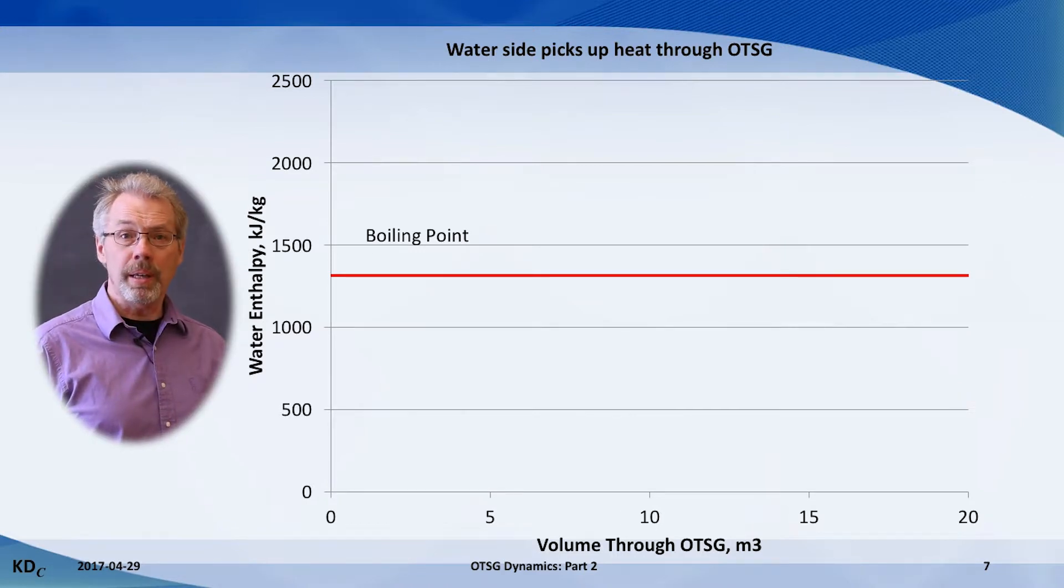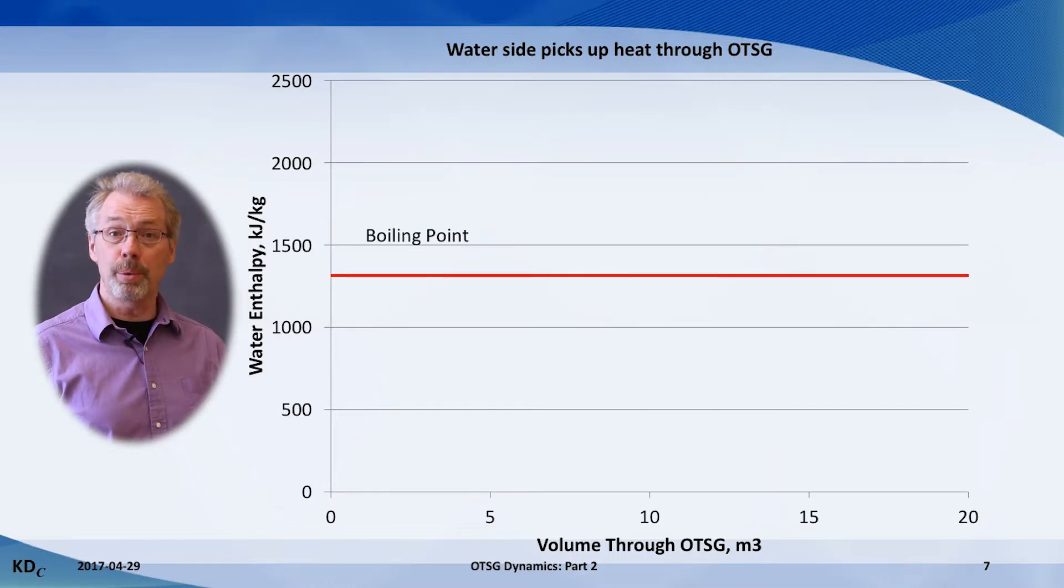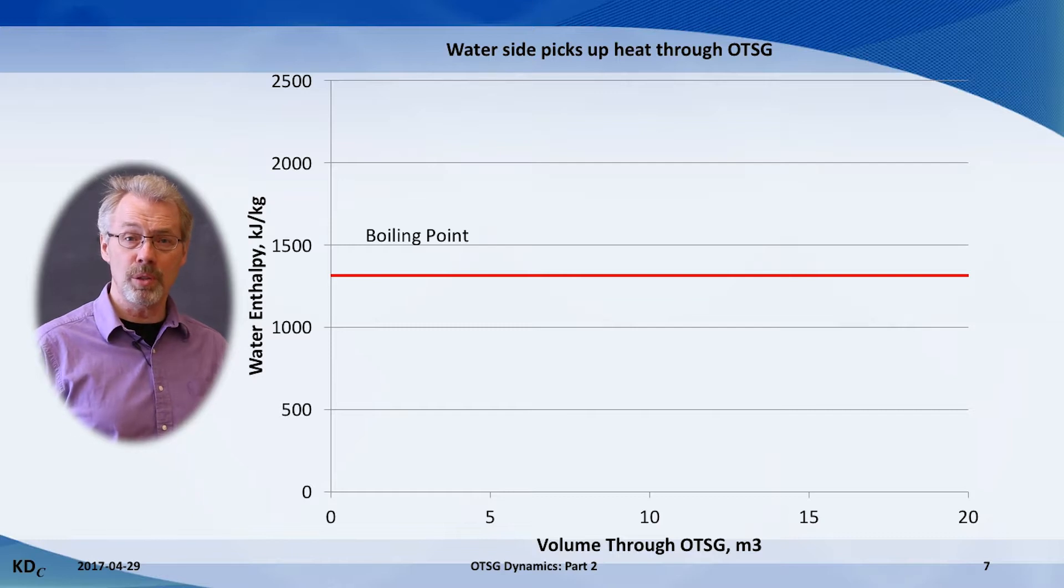This graph will demonstrate how the enthalpy of a lump of water changes as it makes the trip through the OTSG. On the bottom axis is the volume traveled through the OTSG. There's typically 20 cubic meters of volume in an OTSG, with 10 cubic meters in the convection section and another 10 in the radiant section.